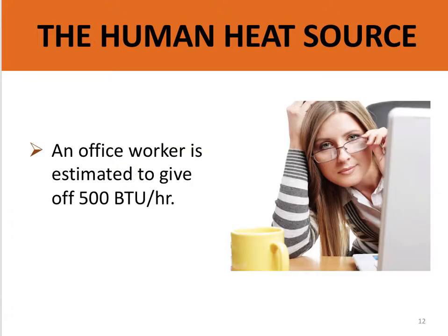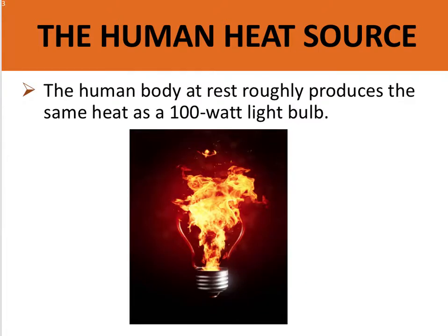An office worker is estimated to give off 500 BTUs per hour. Now remember, BTU is British thermal unit. That office worker will give off 500 BTUs per hour because they're relatively sedentary. The human body at rest produces the same heat as a 100-watt light bulb.